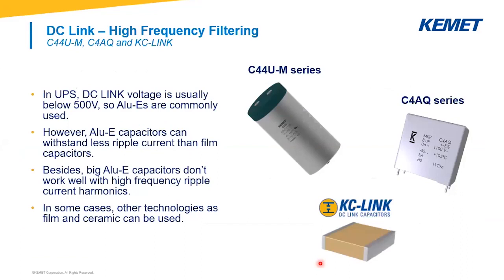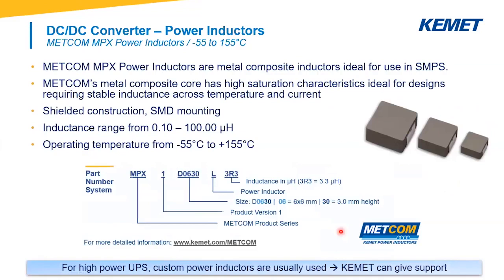UPS DC-Link voltage is usually below 500V, so electrolytics are commonly used. However, electrolytics can withstand less ripple current than film capacitors, and big electrolytic capacitors don't work well with high-frequency ripple current harmonics. So in some cases, film and ceramic capacitors can be used as DC-Link or in parallel with the electrolytics. We offer the C44UM series for high-power screw-mounting applications, the C4AQ DC-Link film box for PCB mounting, and finally our KC-Link — a DC-Link ceramic capacitor with SMD mounting.